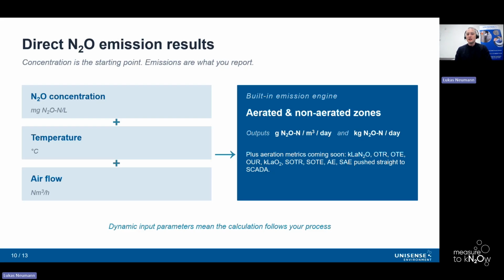Another highlight of this new system is that it can actually calculate dynamic emissions for you. So while a concentration value is interesting, your sustainability team or regulators really want the number in terms of emissions in kilos per day. So this is what the system is able to calculate directly using 3 main points. First, the nitrous oxide concentration from the sensor, then the temperature also using a probe built into the sensor body housing, and the airflow data fed to the connector unit via 4 to 20 milliamps from your aeration system. So this built-in engine handles both aerated and non-aerated zones and is able to differentiate these in the resultant calculation.